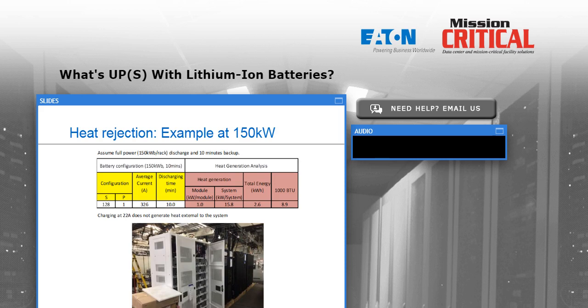Heat rejection. This question comes up occasionally, and we should first say that when the batteries are charging, there is a limit to the amount of charge current that we're allowed to provide with the UPS, and consequently, the amount of heat generated during charging of a discharged battery is almost negligible, barely detectable. But what kind of heat are we giving off during a discharge? Maybe my discharge is 1 hour, maybe it's 15 minutes, maybe it's 5 minutes, but during that time, the system will emanate heat, not much different than valve-regulated lead acid, but as you see in this particular case, on the far right of the table there, about 8,900 BTUs during the time that that battery is discharging. And that's a worst case condition. That's a battery that's discharged at full load for the full amount of backup time.